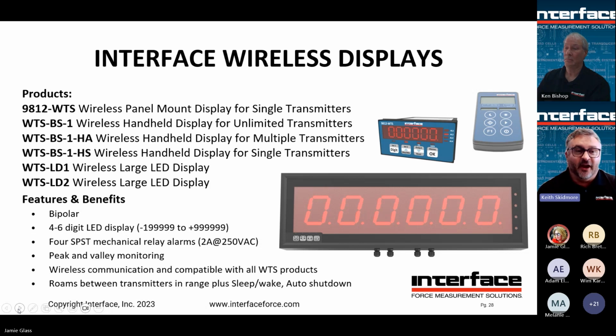For example, you could have a handheld that you're monitoring loads. You could have a panel meter in a panel that's also displaying that load. And then maybe you've got a large display up on the wall so everybody can see the load. All of that can be done with a single transmitter being read by multiple devices. Also wirelessly, you could be logging to a PC for collecting data and analyzing it afterwards.